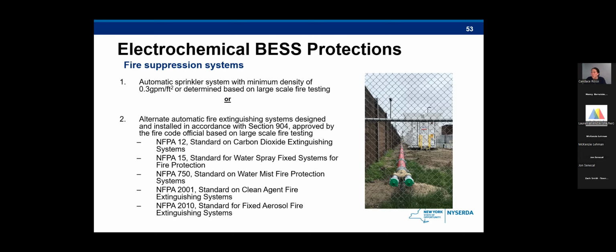So although the code calls out this water density, sometimes there may be a challenge to get that much water density if there's a really tall building and that's where the system is installed, or even in an area that doesn't have good water pressure. So in outdoor locations, some towns are using a dry pipe that the fire department pumper is supplying the water. And this is used so that the automatic water suppression systems do not accidentally freeze or malfunction and cause the water to flow in a system that had no problems. But this would be kind of a conversation between the applicant and the town on what's going to be utilized.